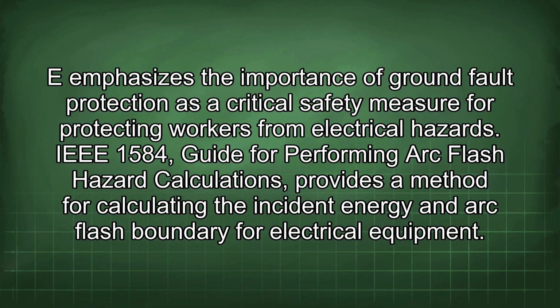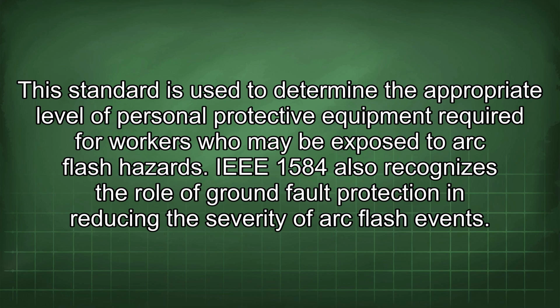IEEE 1584, Guide for Performing Arc Flash Hazard Calculations, provides a method for calculating the incident energy and arc flash boundary for electrical equipment. This standard is used to determine the appropriate level of personal protective equipment required for workers who may be exposed to arc flash hazards. IEEE 1584 also recognizes the role of ground fault protection in reducing the severity of arc flash events.